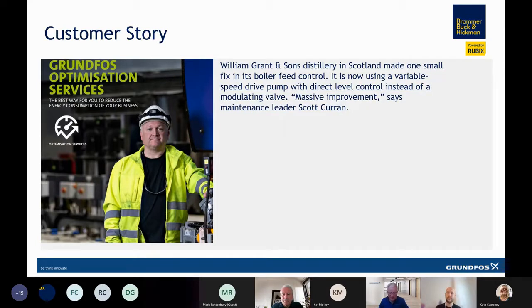But this isn't limited to boiler feed - we've had lots of experiences recently with cooling towers. We're basically putting variable speed pumps on cooling towers, able to control the pumps on differential temperature, and there's enough intelligence in the pumps to operate the fans as well. Fans only need to operate when the ambient temperature is over 25 degrees C, so if we can use the pumps to control those, it's a huge efficiency and energy saving, perhaps up to 50%, and we've seen cases of payback within 10 to 14 months.